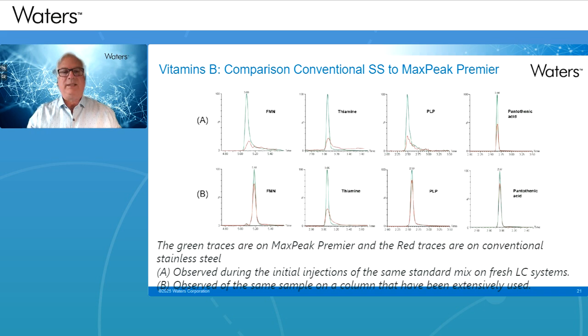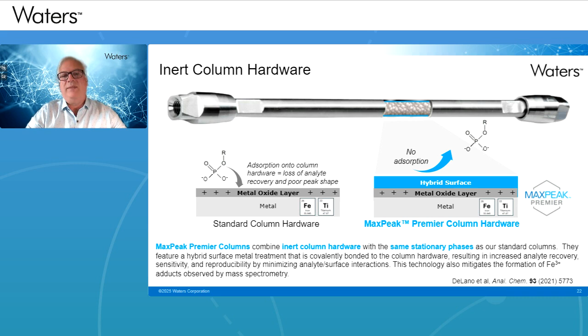So what is the MaxPeak column exactly? It's an inert column hardware. So all the metallic surface, not only the tube, but all the frit and everything that comes in contact with the sample has been chemically modified. So covalently bonded, the surface is hybrid, is no more metal oxide layer, and it is protecting the column forever. I mean, it will not leach, it will not bleed, you will not observe any deterioration of the column with time. It's just that it's a new surface that is in contact with the molecules. One of the benefits will be in mass spectrometry.